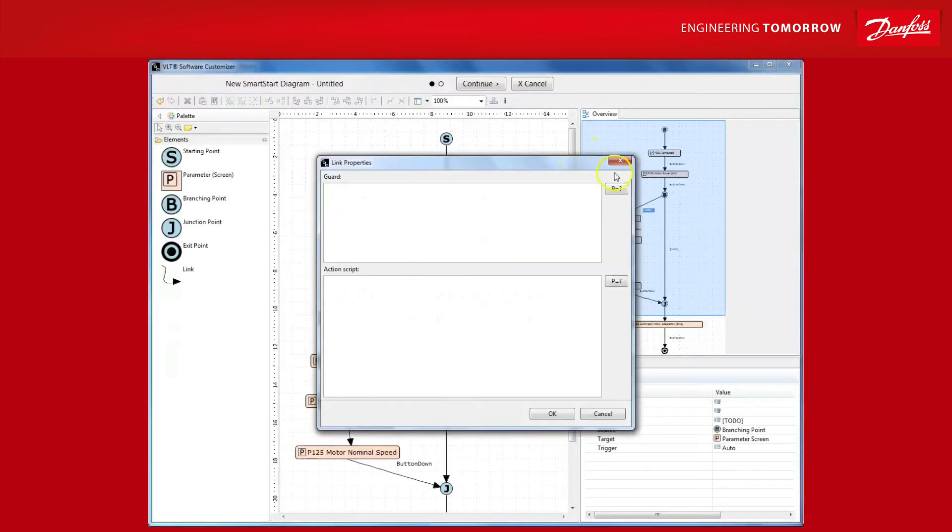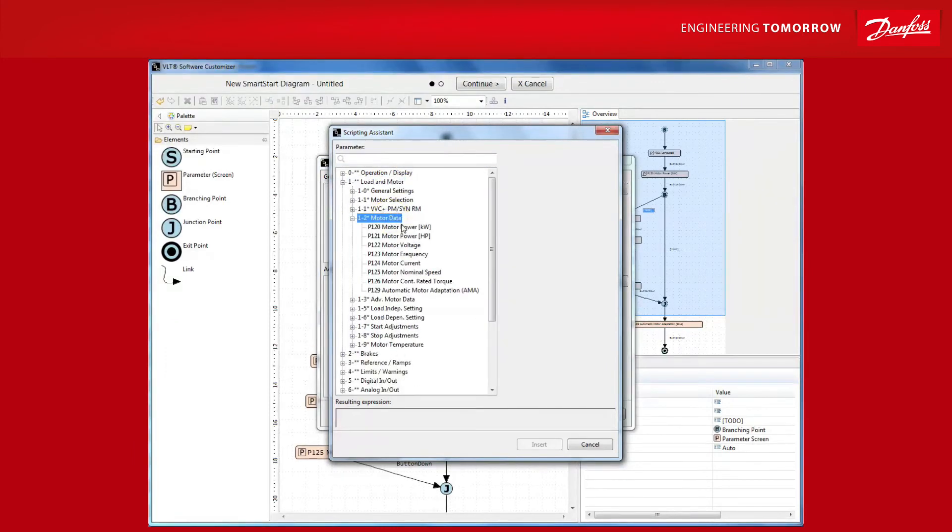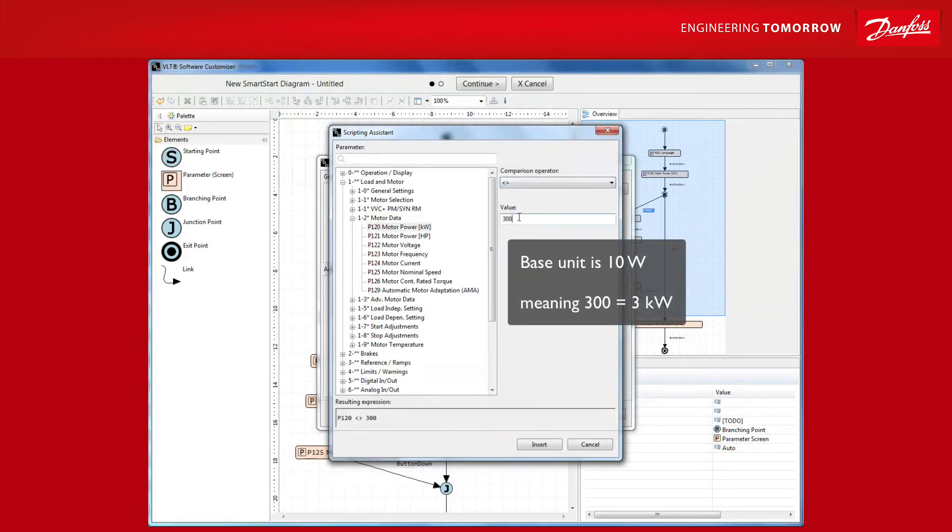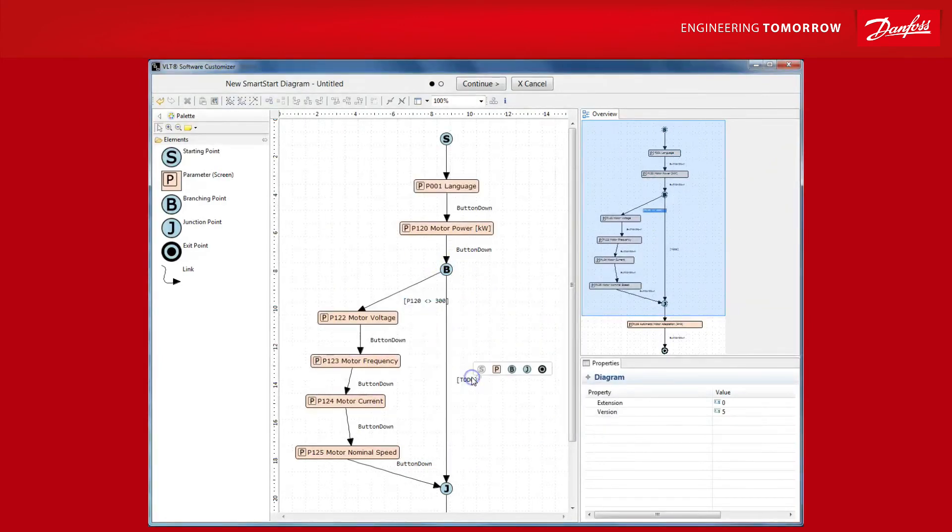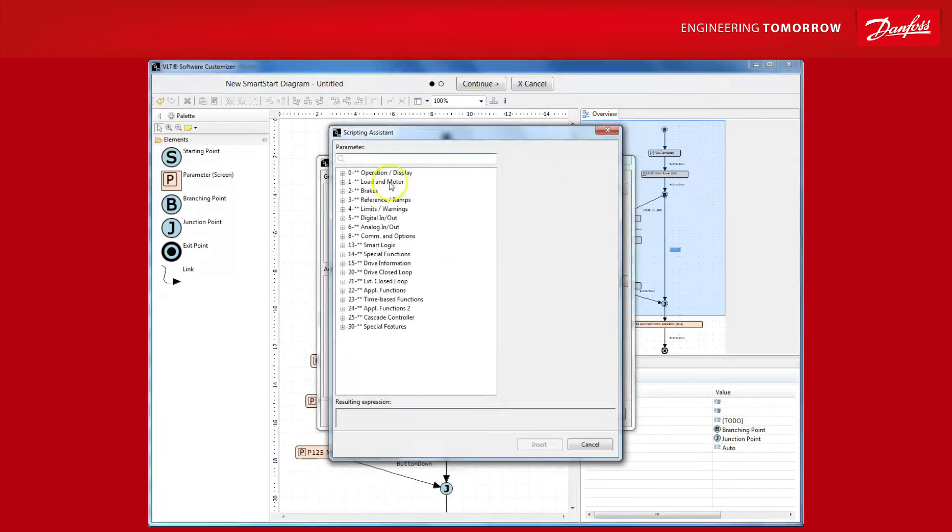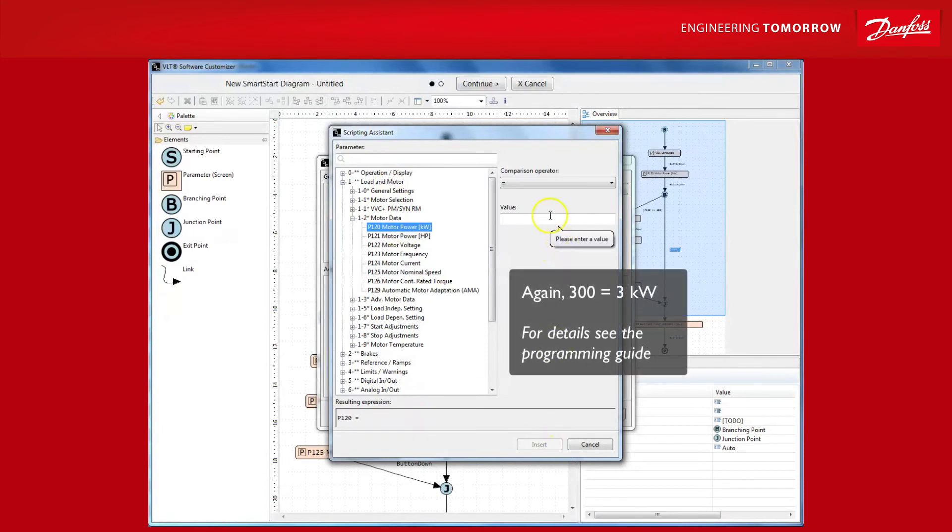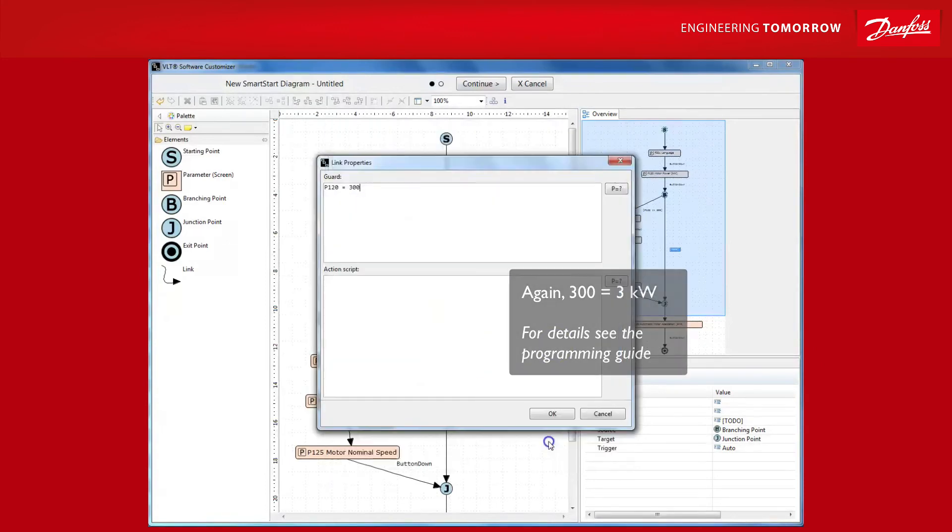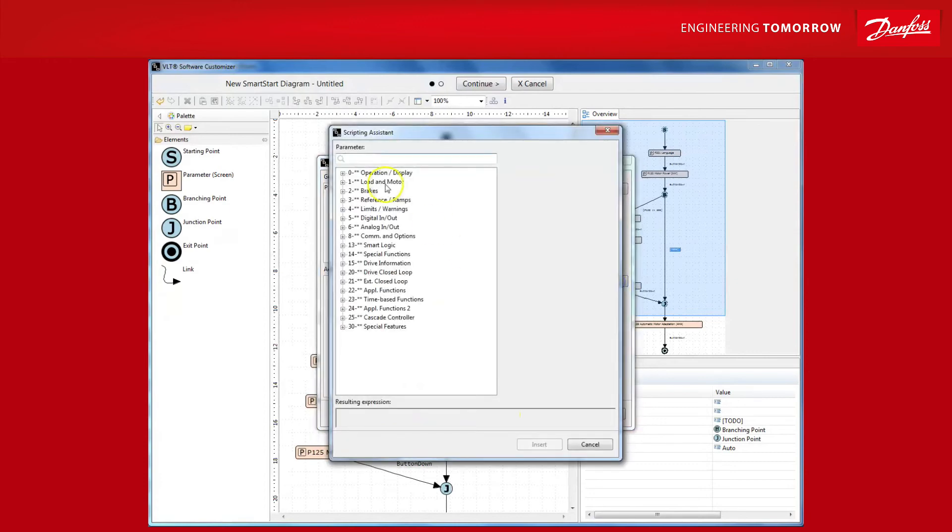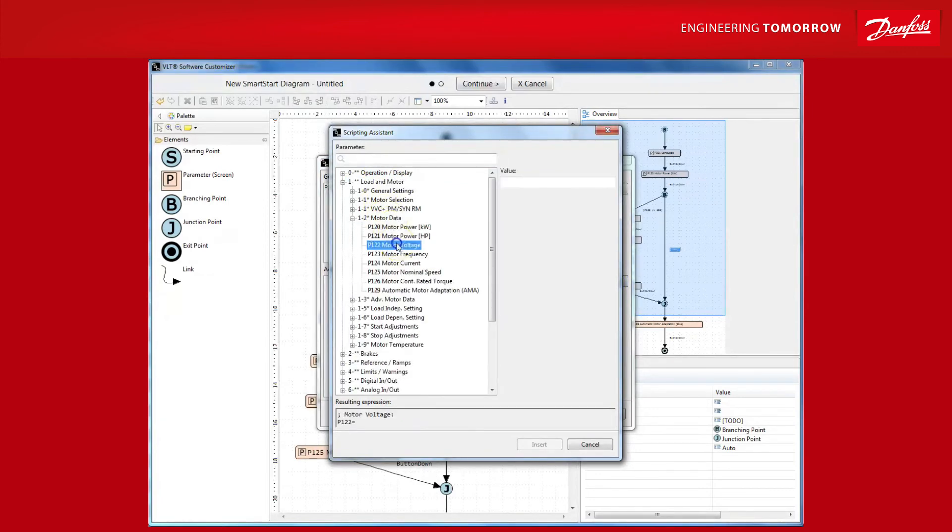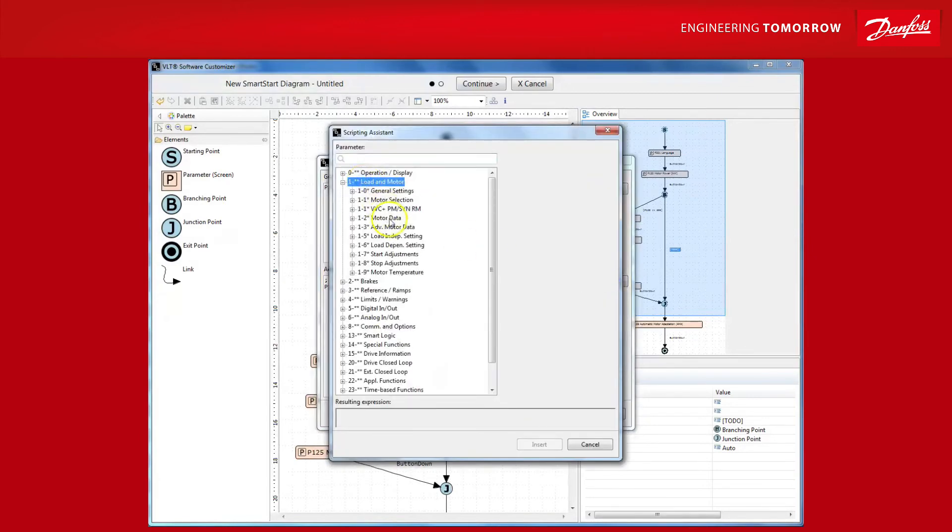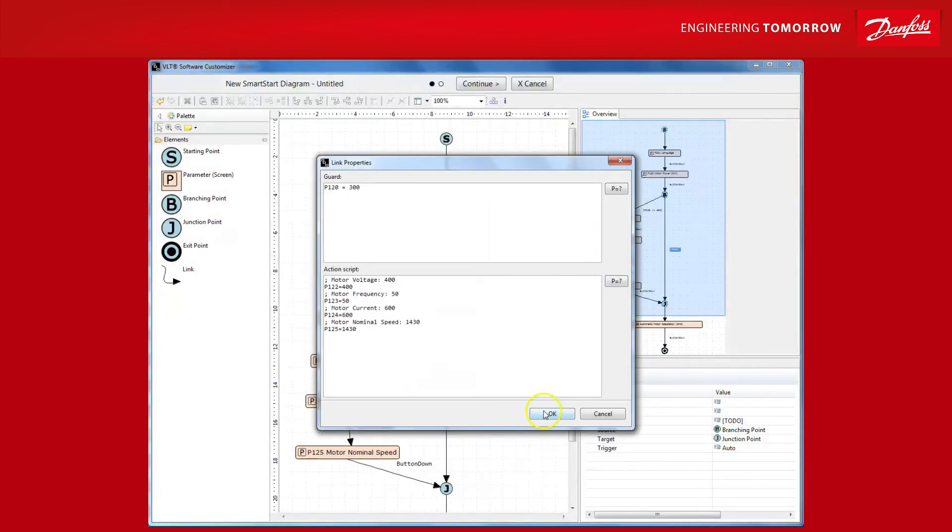Double click the to do label and find the parameter for motor power, which the user will just have input. We will pick the smaller or bigger than operator, meaning that anything that is smaller or bigger than 3kW will take this path. Now, let's do the same for the right path, only here we will select equal to 3. Here in the input field below, we get to decide any action the wizard should take automatically, and as I mentioned in our example, we use a 3kW motor. It is always the same one, so we know the motor data upfront. So, you input all the values you need, the motor voltage, motor frequency, motor current, and the motor nominal speed.